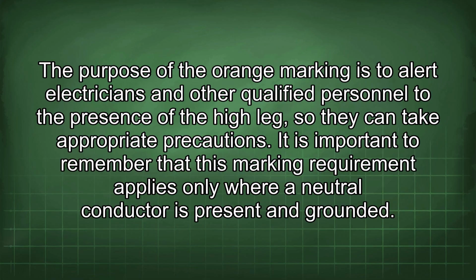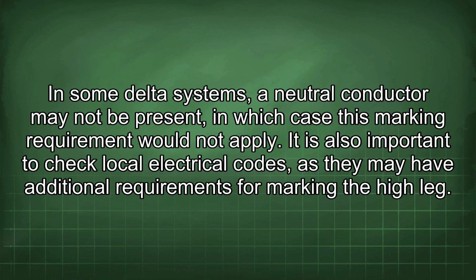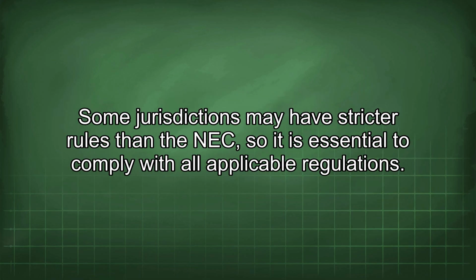It is important to remember that this marking requirement applies only where a neutral conductor is present and grounded. In some delta systems, a neutral conductor may not be present, in which case this marking requirement would not apply. It is also important to check local electrical codes, as they may have additional requirements for marking the high leg. Some jurisdictions may have stricter rules than the NEC, so it is essential to comply with all applicable regulations.